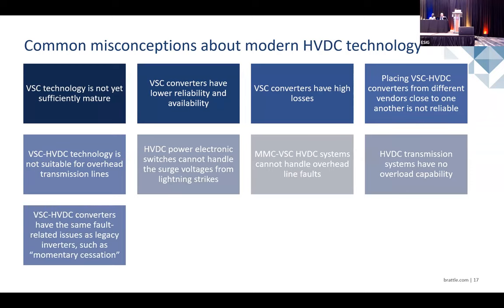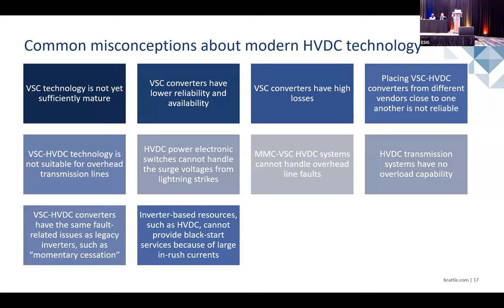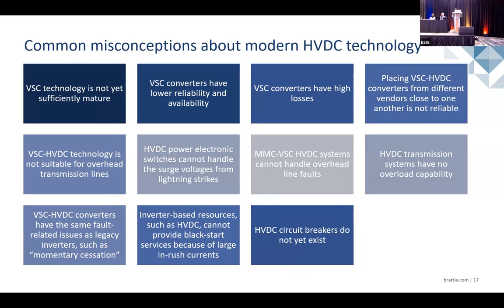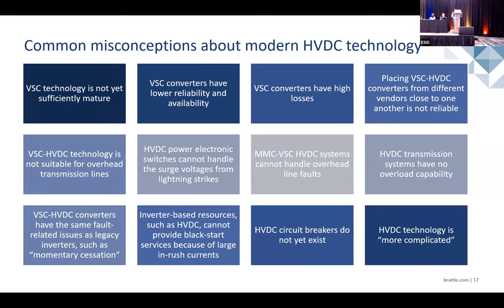Next is the behavior of the converters during fault events, like over voltage or under voltage. Again, this area is very matured, and many projects in Europe were delivered based on these requirements. HVDC can also help support black start. In projects in operation in Europe, VSC converters were utilized to restore the networks. There are real examples from Europe on this front. When we go to multi-terminal, for sure we need a DC breaker. This area is evolving. We don't have a lot of experience, but things are evolving. And of course, HVDC technology is more complicated, that's for sure, but we are gaining a lot of learning and things are becoming better.